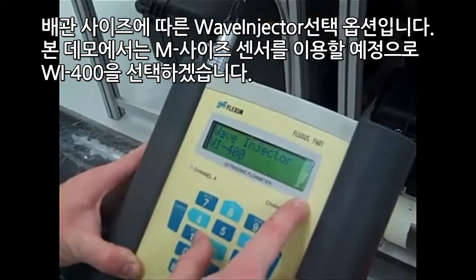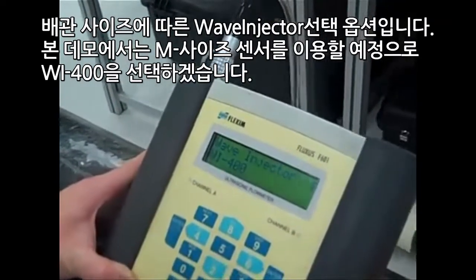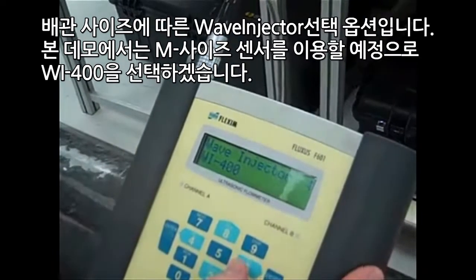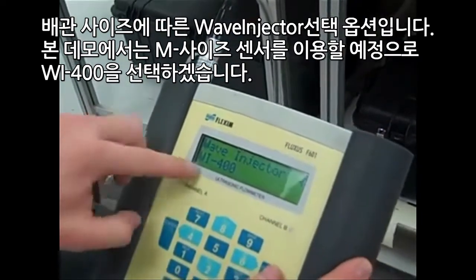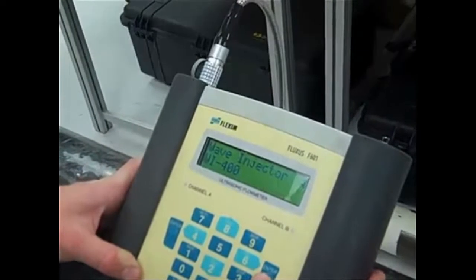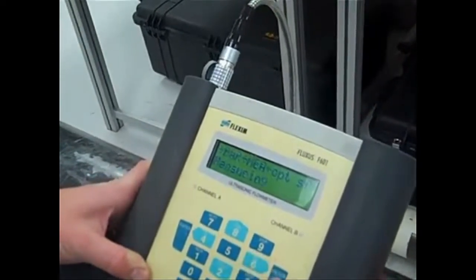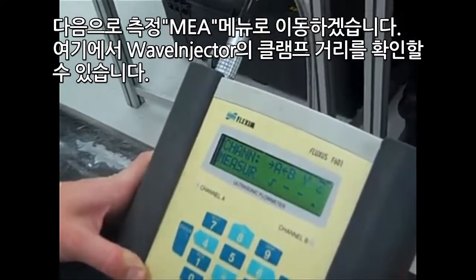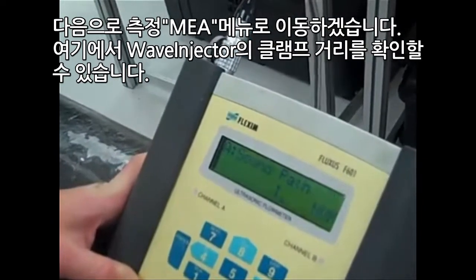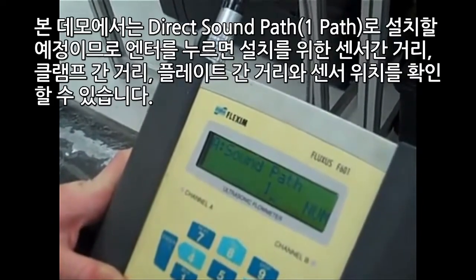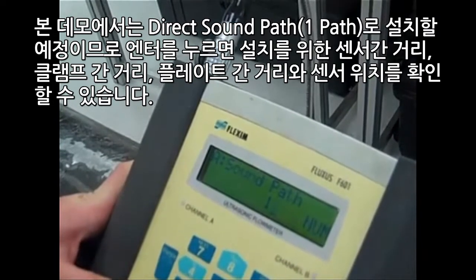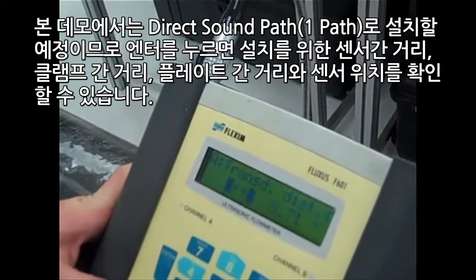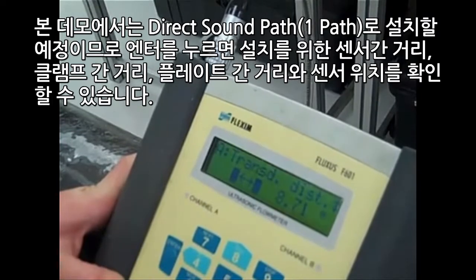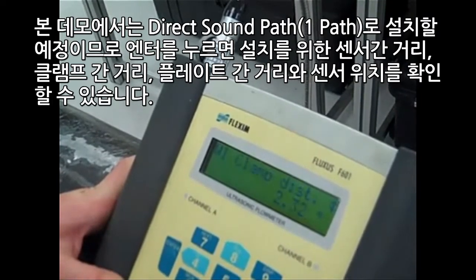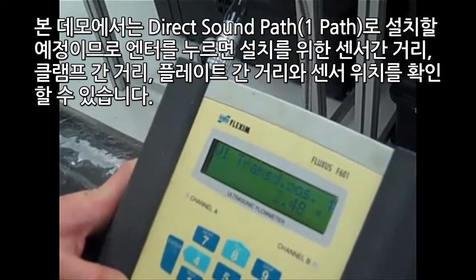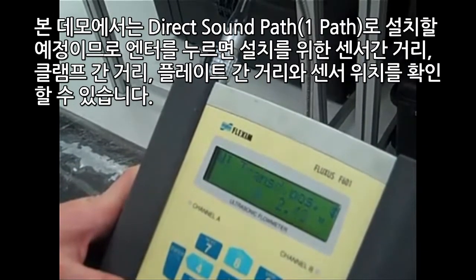Depending on your pipe size, this is where you select the kind of WaveInjector you're using. This is an 8-inch pipe using M size transducers, so we're going to be using the WaveInjector 400. Next, you go to measure, and this is where you get your clamp distances and your WaveInjector spacings for the application. We are going to be installing a direct sound path, so enter 1 in for the sound path, and this is where you get all your spacings: your transducer distance, your clamp distance, plate distance, transducer position.